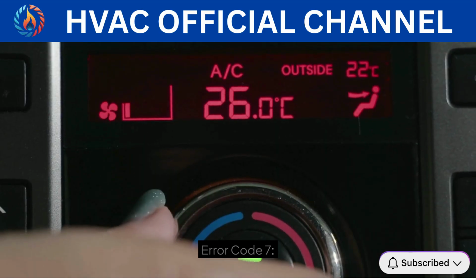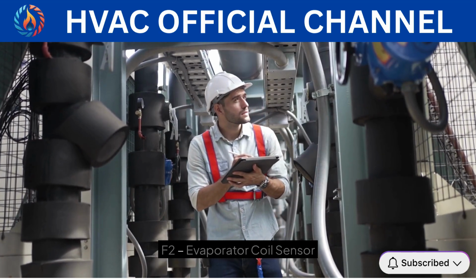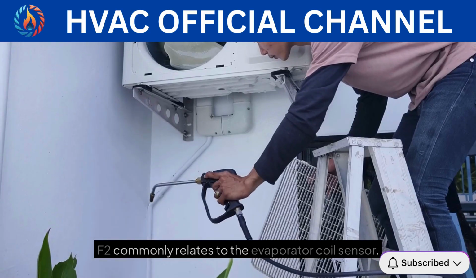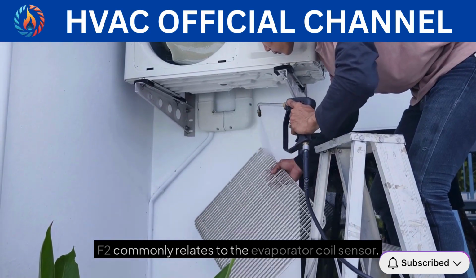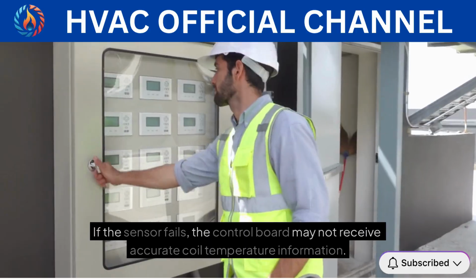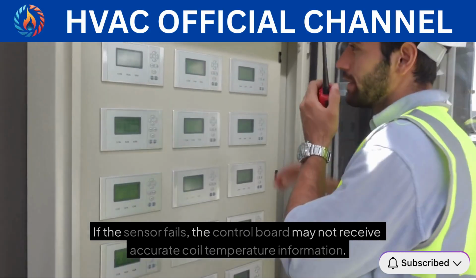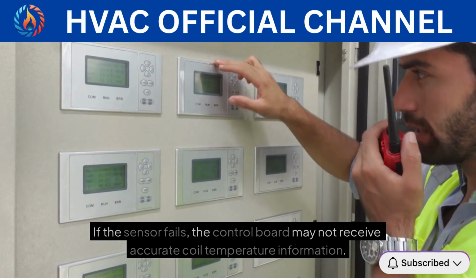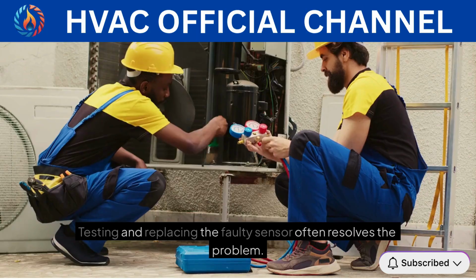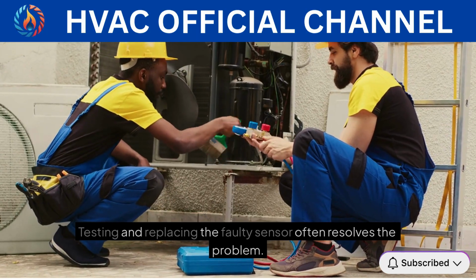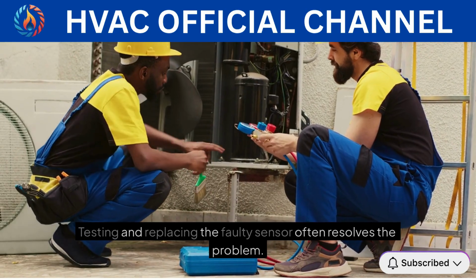Error code 7, F2, evaporator coil sensor error. F2 commonly relates to the evaporator coil sensor. If the sensor fails, the control board may not receive accurate coil temperature information. Testing and replacing the faulty sensor often resolves the problem.